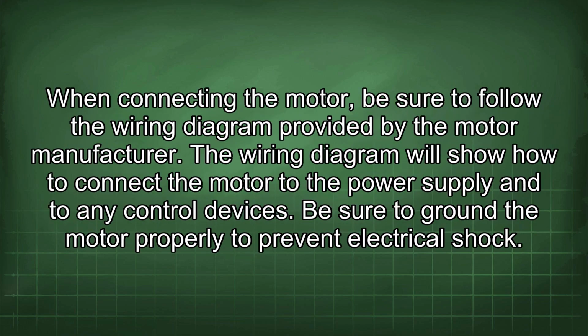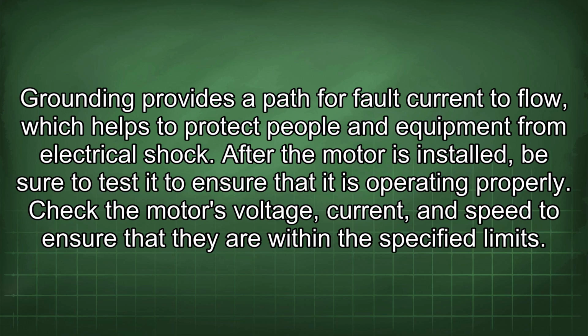When connecting the motor, be sure to follow the wiring diagram provided by the motor manufacturer. The wiring diagram will show how to connect the motor to the power supply and to any control devices. Be sure to ground the motor properly to prevent electrical shock. Grounding provides a path for fault current to flow, which helps to protect people and equipment from electrical shock. After the motor is installed, be sure to test it to ensure that it is operating properly.